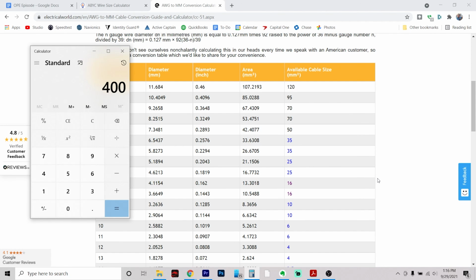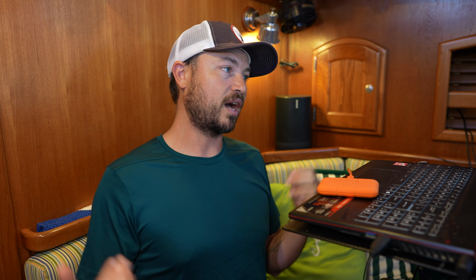So the most sensible fuse for us to use is a 400 amp fuse, because 400 divided by 300 is 133%. So that's right there within that range of between 125% and 150% of the load. So we've got dual 3-aught cable and we've got a 400 amp fuse for that circuit.